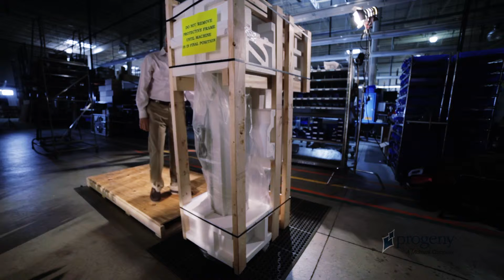For wall mount installation, begin by reviewing the requirements for the wall mount and fastening kit. The exact requirements are detailed in the Quick Start Guide under Step 4. Be sure that the wall mount is level, and note that the mounting holes are slotted for installation. The main column will be attached to the wall mount 47.5 inches from the floor. After mounting the wall mount bracket, snap the column in place.